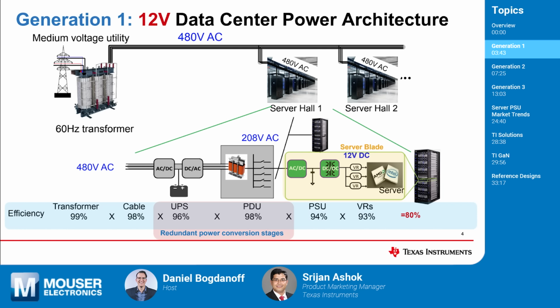What happens is that rack on the right has multiple shelves, or blades as we call it. In that shelf, the AC power goes in, and there's an AC to DC conversion which gets it down to 12 volts DC. That's then given to the next stage of conversion, which eventually powers up the GPUs of the future, or CPUs of the past, whichever is the central processing unit. So the 12 volt is generated and then further regulated down to the CPU voltage level, typically 1.8 volts or 1 volt, depending on the CPU, there can be many different voltage levels.